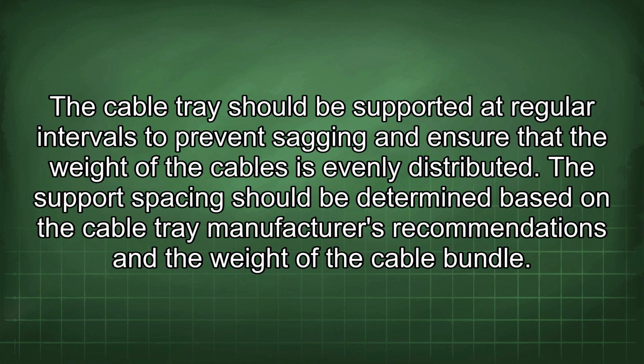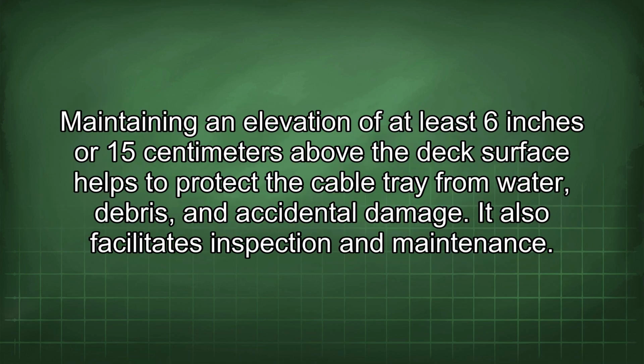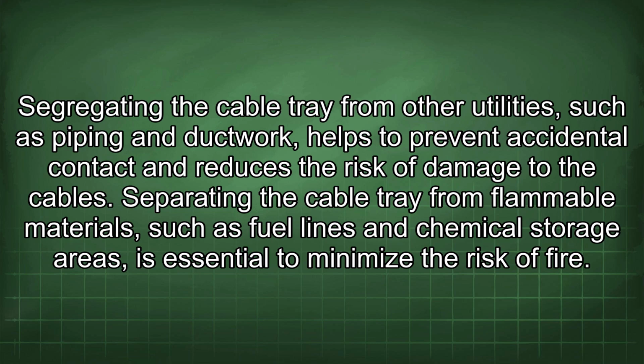The cable tray should be supported at regular intervals to prevent sagging and ensure that the weight of the cables is evenly distributed. The support spacing should be determined based on the cable tray manufacturer's recommendations and the weight of the cable bundle. Maintaining an elevation of at least 6 inches or 15 centimeters above the deck surface helps to protect the cable tray from water, debris, and accidental damage. It also facilitates inspection and maintenance. Segregating the cable tray from other utilities such as piping and ductwork helps to prevent accidental contact and reduces the risk of damage to the cables.